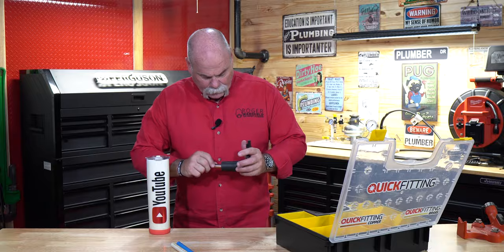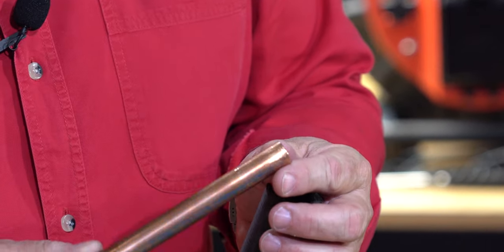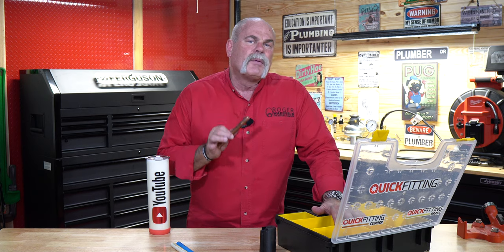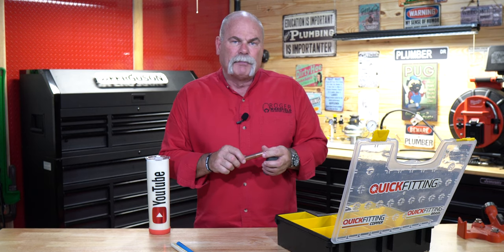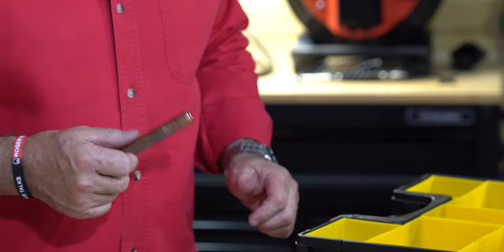Now let's do the copper. If you look at that you can see that bright shiny edge where it's been reamed down, and you've got a mark right down here. To me this is one of the most important things that people skip when it comes to push-to-connect fittings. What I like is the fact that Quick Fitting has made a tool that does two things: it bevels the outside edge and it gives you a clear mark so you know it's inserted to the full depth.